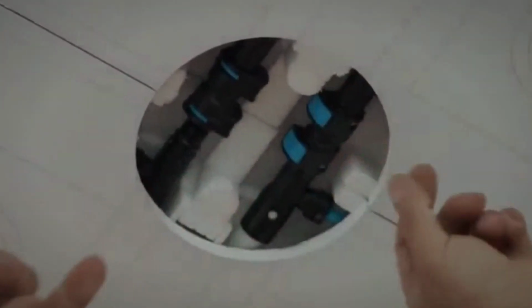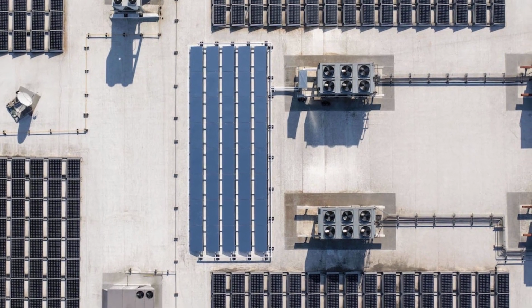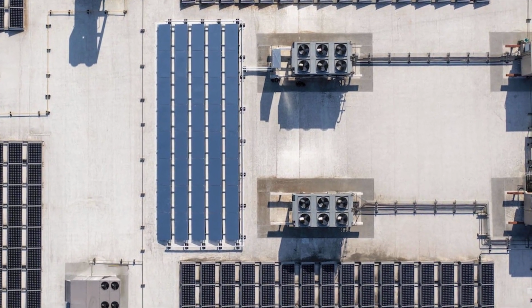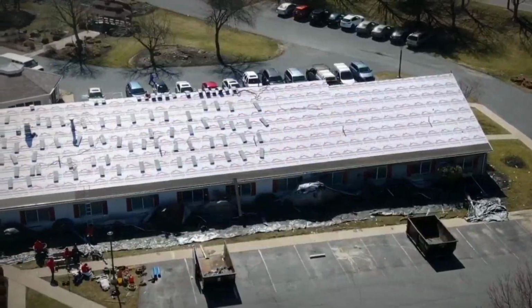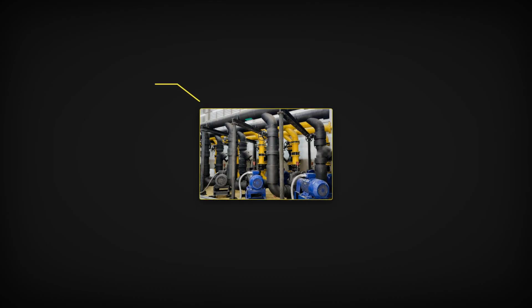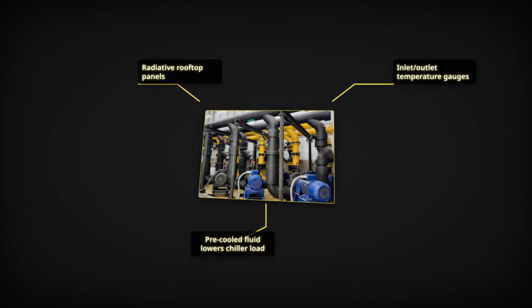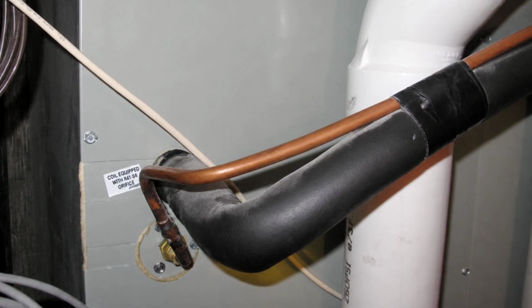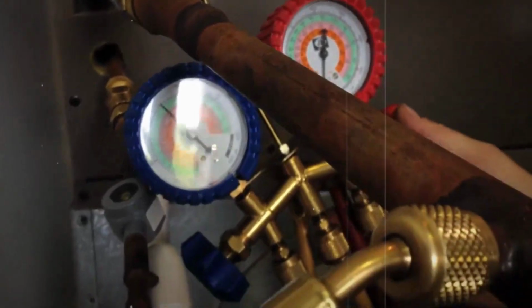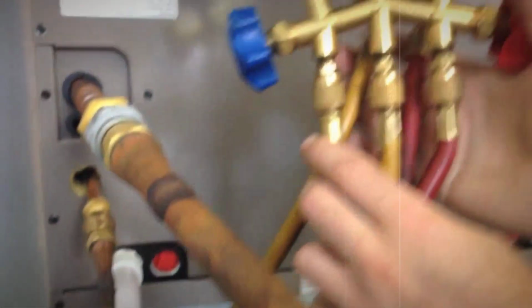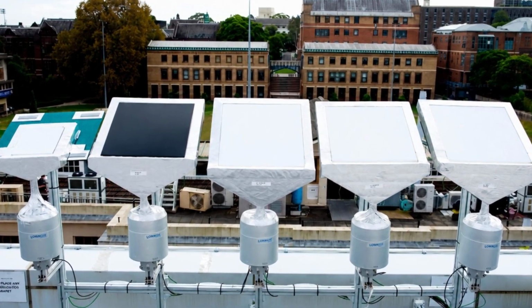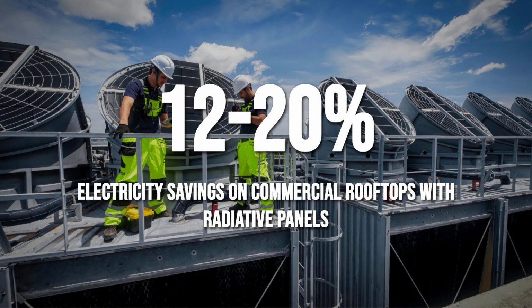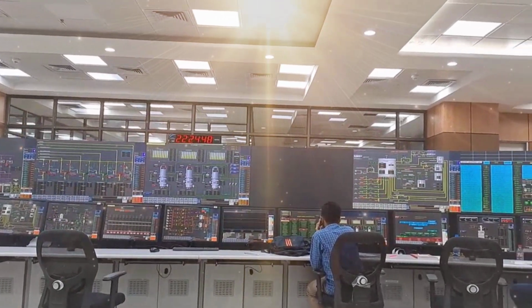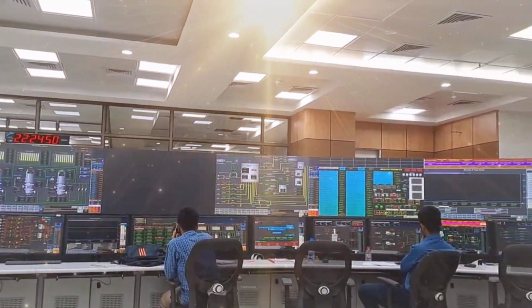Commercial systems have also used radiative panels to assist conventional air conditioning and refrigeration equipment. Instead of attempting to cool an entire building directly, the panels cool circulating fluid before it reaches the mechanical refrigeration system. By lowering the fluid temperature in advance, the compressor has less work to perform. Testing on commercial buildings has reported electricity savings in the range of approximately 12% to 20% under favorable conditions. That hybrid approach may be one of the most practical uses of the technology.